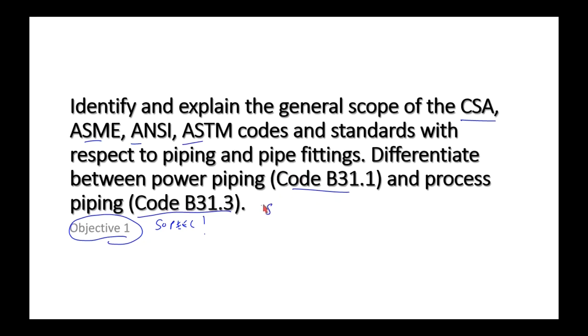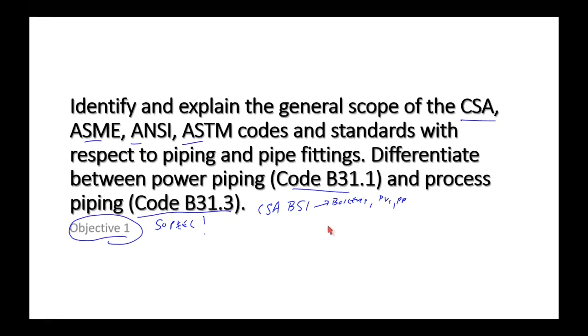The CSA is a Canadian code — specifically, it's the B51, which covers boilers, pressure vessels, and pressure piping. Because CSA is a Canadian code, it supersedes all other codes and standards that are referenced, including the ASME. But it references many codes, including the ASME Boiler and Pressure Vessel Code.